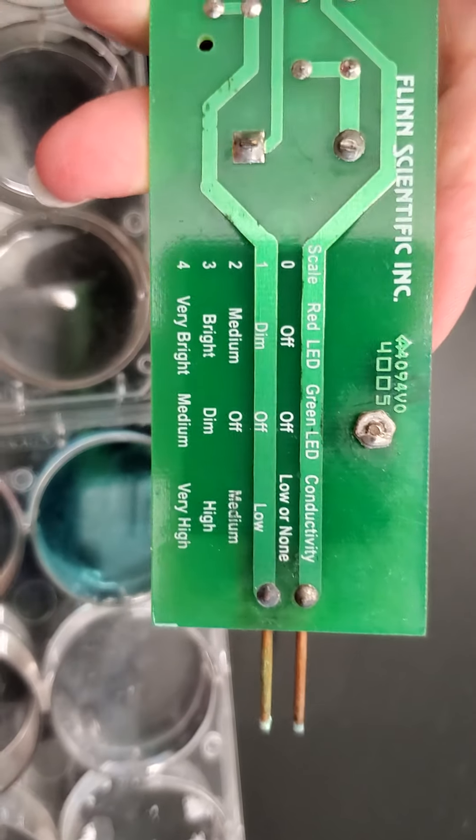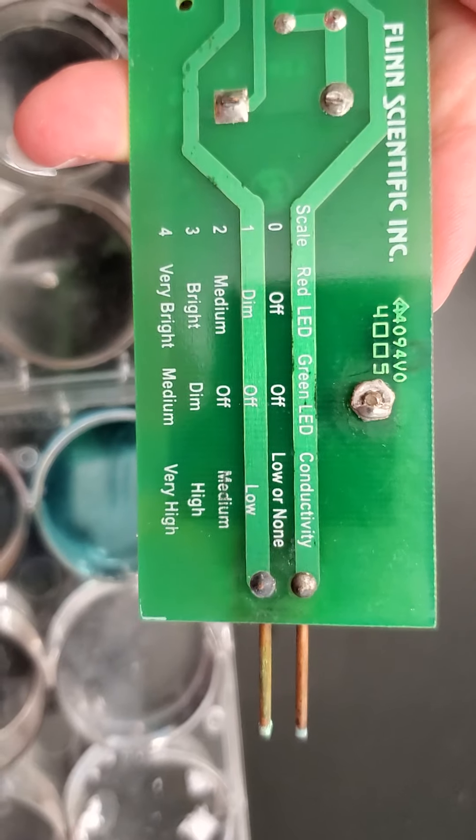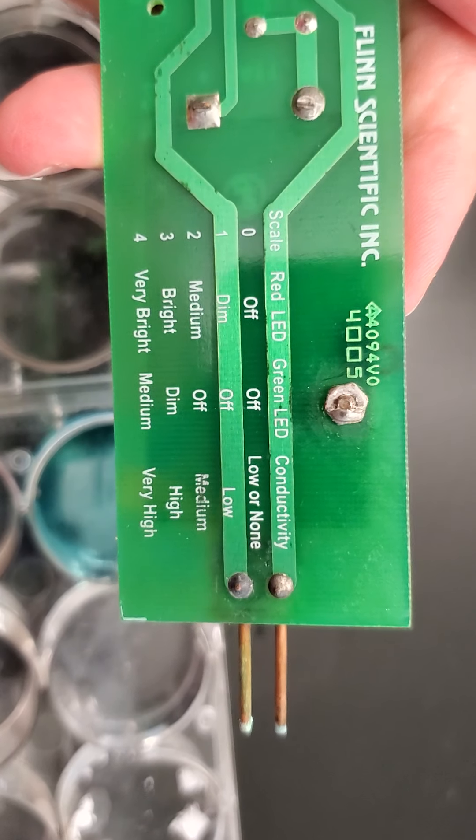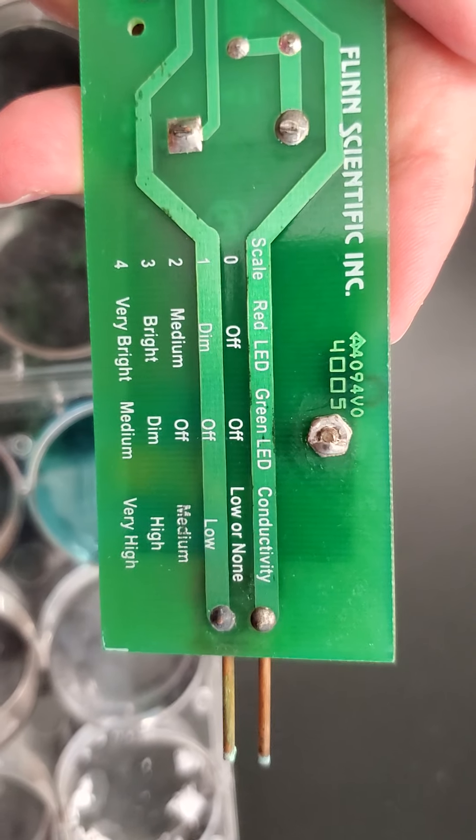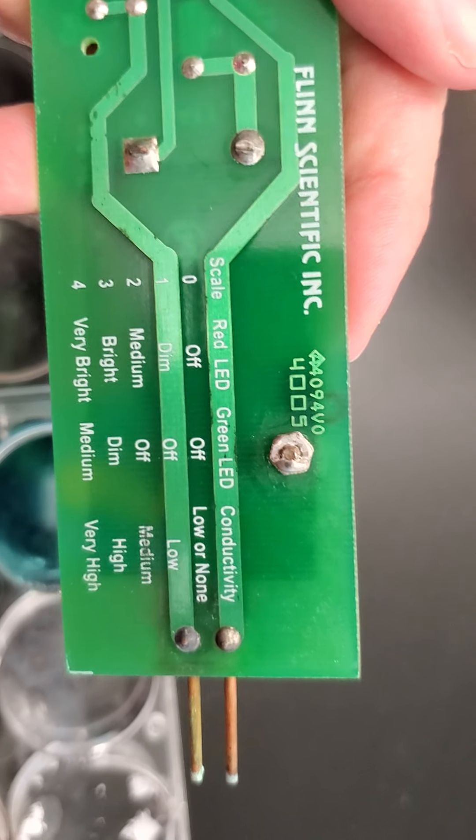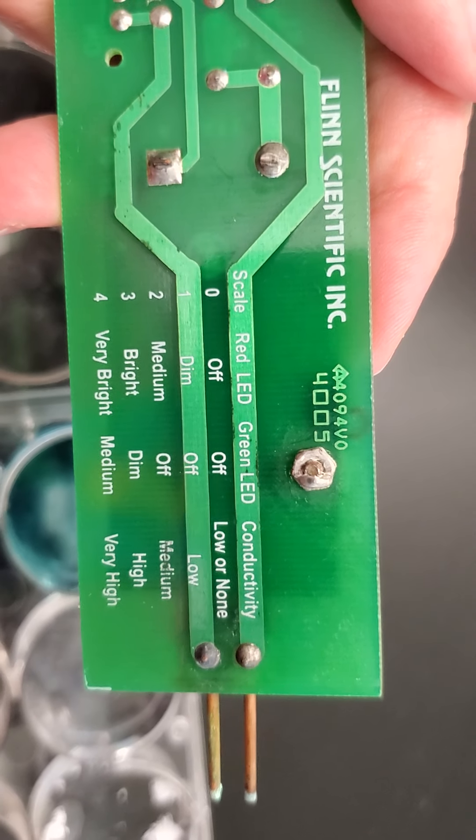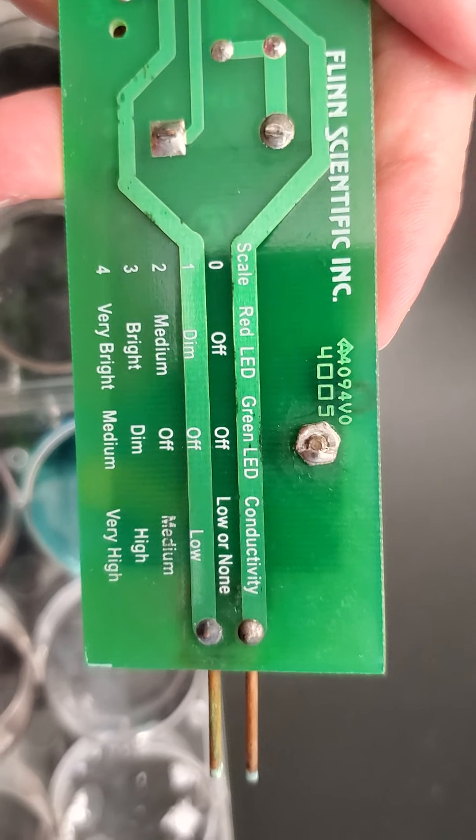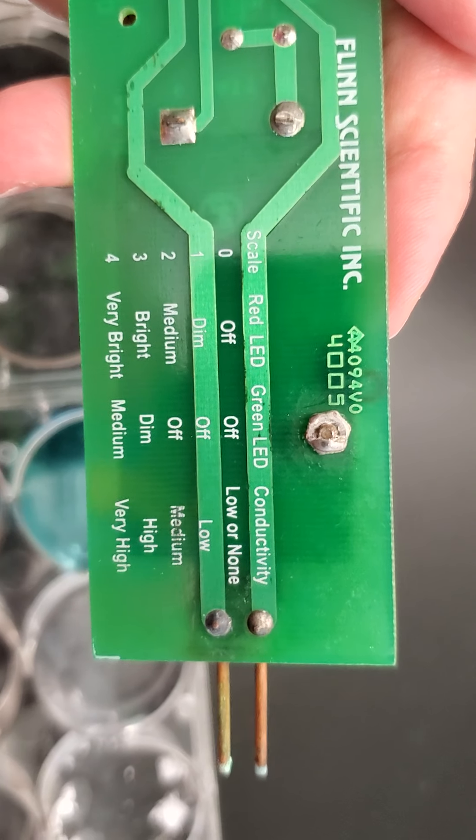It has a little guide at the back. If either light doesn't turn on, it's low or no conductivity. If it's dim on the red and the green stays off, then it's low. If the red looks medium and the green is still off, it's medium conductivity.